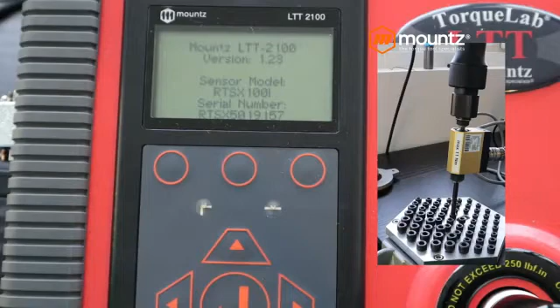Let's go ahead. What we see here is that the values with the rotary sensor are basically higher than with the static sensor, so there's a difference between both types of measurements. This matters because we want to know what torque is really applied on the part, and the dynamic sensor helps us with that.